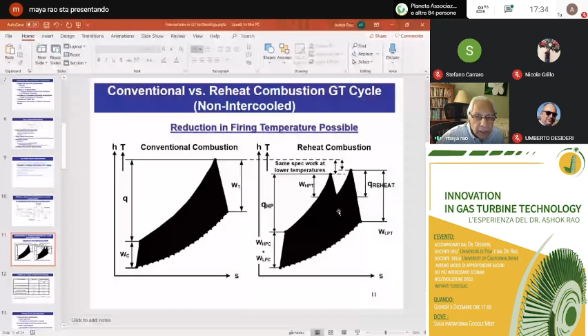In fact, I want to show some numbers here on the next slide, which shows a comparison between the GE 7FA, General Electric 7FA gas turbine performance, compared to what used to be Alstom GT24, which is a reheat machine. This is, of course, now owned by GE also. It shows the firing temperature and the efficiency. The efficiency is, in fact, very similar for the two engines here. But as you can see, the firing temperature is much lower for the reheat machine. So this is one approach to getting high efficiency without having ultra high firing temperatures.